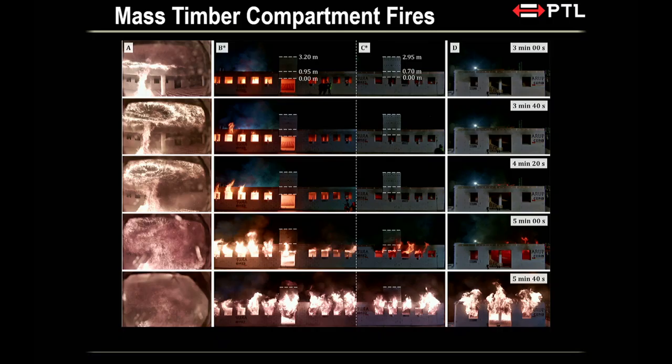All right, so in terms of fuel load, we have low-level wood cribs inside the compartment. These are often standard fuel load that we use for fire. The fuel loading here is equivalent to what you would have in a residential setting, right? So imagine this is someone's house. The walls of these compartments are all concrete. The ceiling is CLT, okay?